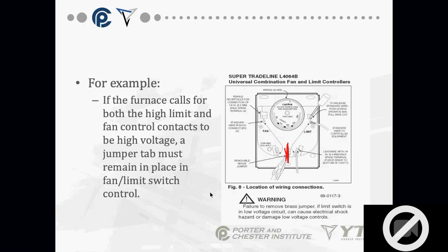Okay? If the furnace calls for both high limit and fan controls on the high voltage side, we leave the jumper tab in place. If we remove the jumper tab, I now can be using two different voltages or two different circuits. Be very aware of this when you have to replace a fan limit switch. Okay, when they come from the supply shop set up for high voltage, the jumper tab will be in place. To go to a low voltage, you have to pull the jumper tab out. You have to remove it.